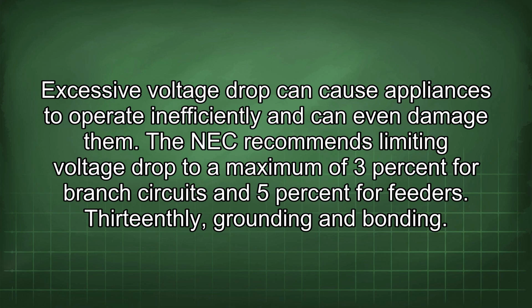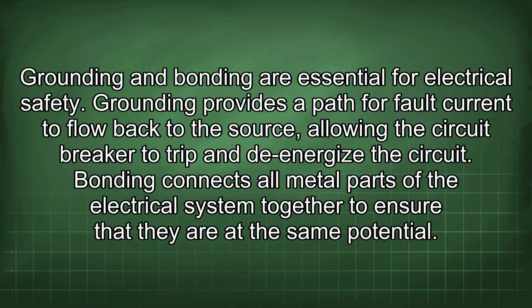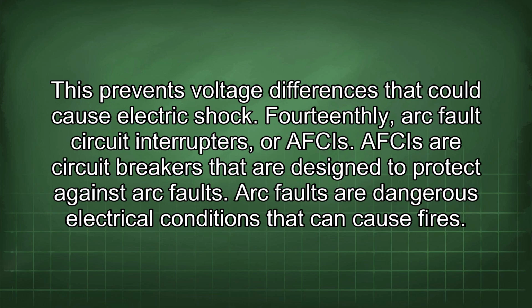Thirteenthly, grounding and bonding. Grounding and bonding are essential for electrical safety. Grounding provides a path for fault current to flow back to the source, allowing the circuit breaker to trip and de-energize the circuit. Bonding connects all metal parts of the electrical system together to ensure that they are at the same potential. This prevents voltage differences that could cause electric shock.